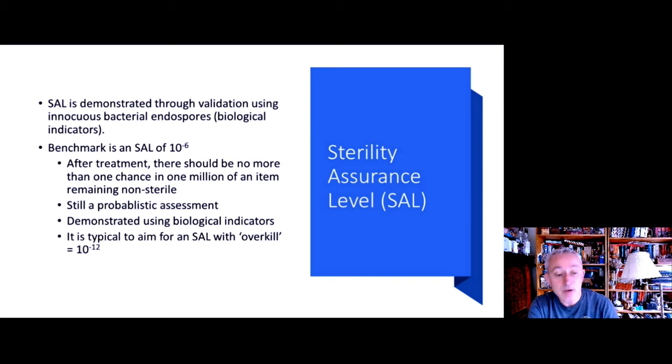So we can demonstrate the sterility assurance level by using spores in a special preparation called biological indicators. And we're expressing the SAL as a negative fraction. That's why it's written as 10 to the power of minus 6, because we're talking about reducing a population downwards rather than increasing. So if we had one microorganism in a bottle of broth and we wanted that microorganism to grow, we'd be moving upwards and we might express that as 10 to the power of 6. But because we're discussing the destruction and elimination of microorganisms, we express this as a negative value. And we're demonstrating that through the use of biological indicators.